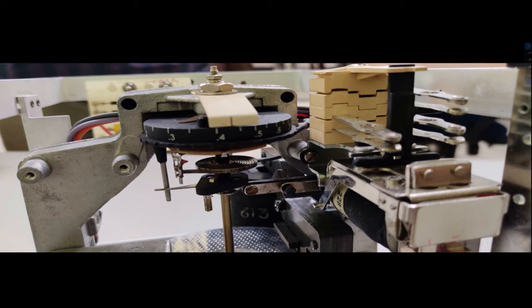This spindle carries that elongated, projected part, and when the disc rotates, the spindle as well as this portion also rotates. Ultimately, this portion touches here and creates pressure on those two portions, and ultimately the switch becomes closed, and only then is the tripping coil energized. Now here you see that particular dial carries one projected part also, and this portion touches that projected part. This is actually called the backstop of the disk. So the disk is not free to rotate beyond a certain portion, due to that projected part from the dial and these arrangements.